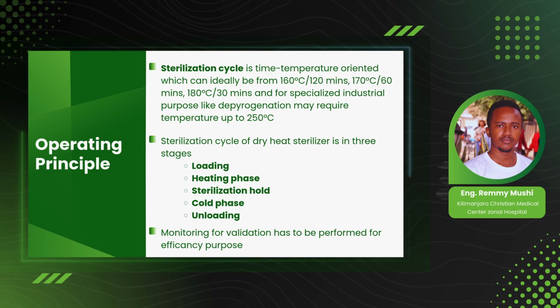In most cases we have a temperature around 160 to 180 degrees for this dry heat sterilizer. But for special cases, such as in the pharmaceutical industry, we will need a temperature of up to 250 degrees. This is because of a process called depyrogenation, which is a way of deactivating or destroying the pyrogens, the agents that can cause fever, inside the chemical compounds which are used for the manufacturing of drugs.